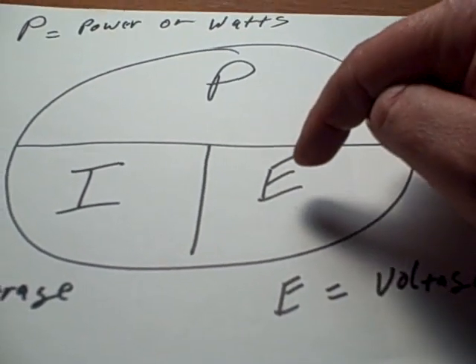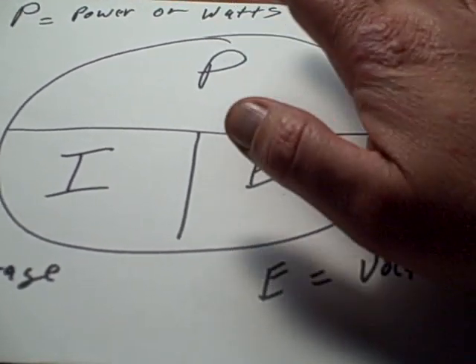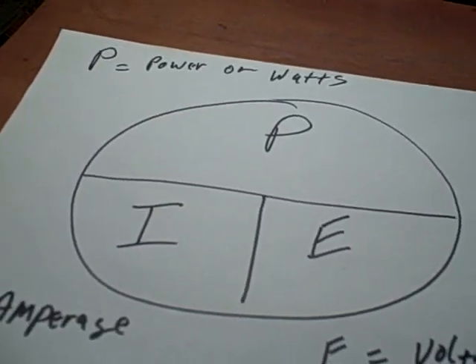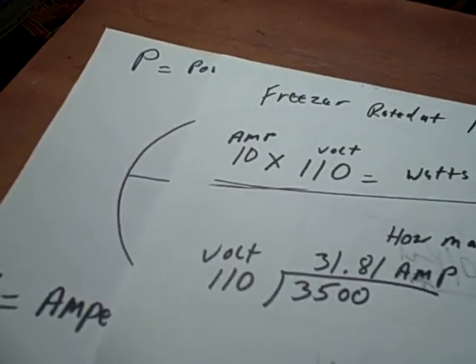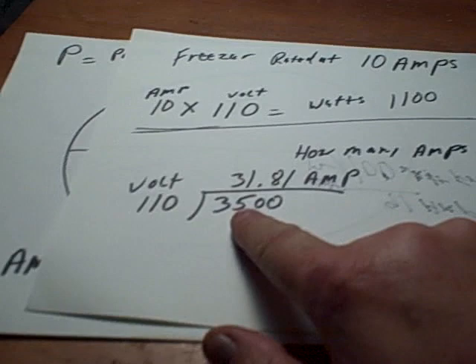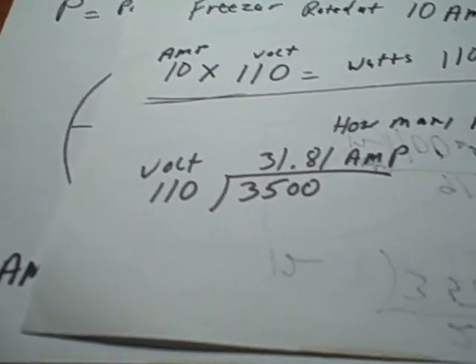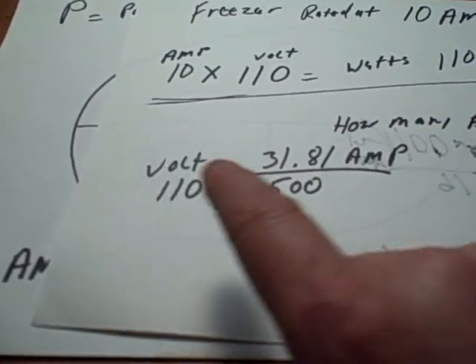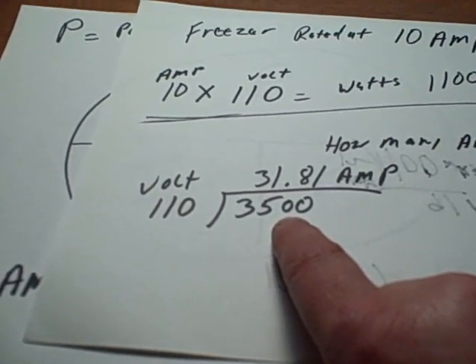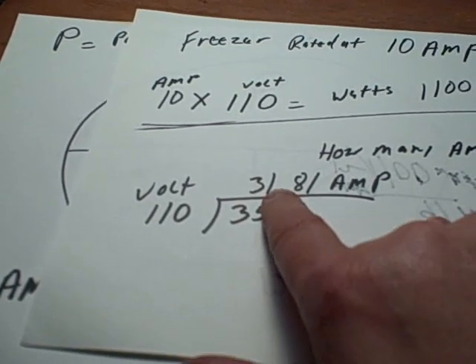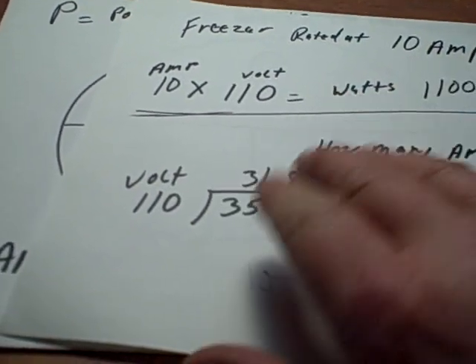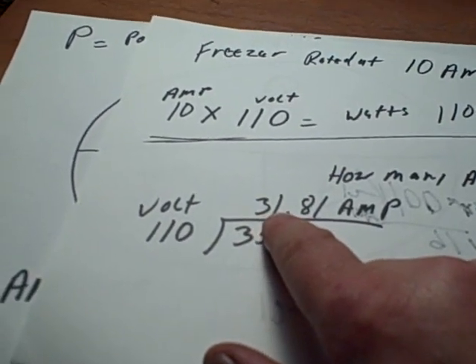I've done that here on this sheet. Okay, here's where I did it. At 110 volts I have a 3500 watt generator. That will give me at full load, of course there's a 4000 peak but we're not counting that, they give me about 31 amps, 31.8 amps.